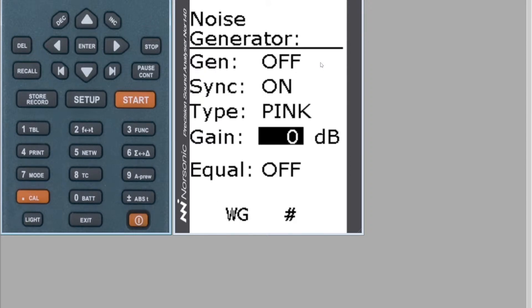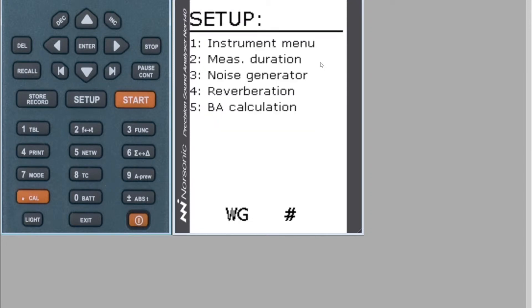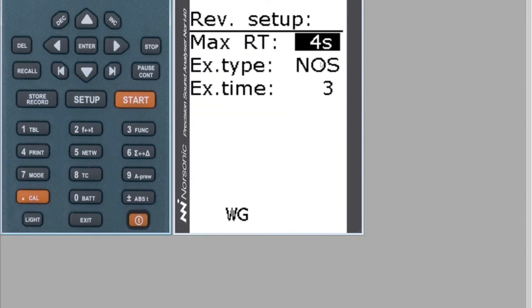To go back out of the Noise Generator menu, press the Enter key and it brings you back to Setup. To set the reverberation methods, press button number four. In here you can set the type of noise. I'm using NOS, which means the signal is generated in the meter and sent down the signal cable to the speaker. It will measure the decay automatically — it triggers the speaker, fills the room with pink noise, then turns off the speaker, and the meter measures the decay.